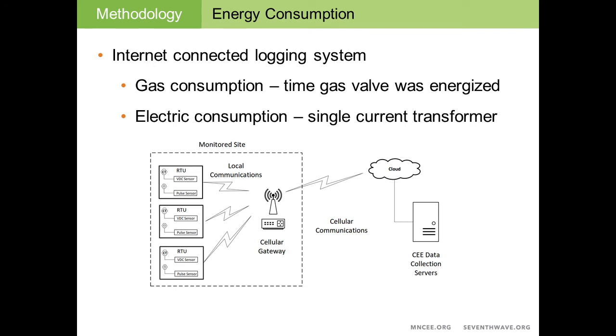The 2 main energy streams that we're looking for in rooftop units are the gas consumption and the electrical consumption. Traditionally, if you were to put a standard logger on the roof and install a gas meter, redo the gas lines in order to get the gas consumption, and then also install a power meter, that's going to be an extremely expensive endeavor when you start looking at the number of rooftop units and sites that we wanted to monitor. So CEE took a different approach where we decided to time the gas valve. By knowing how long the gas valve is operational, and by knowing the input rate of that gas valve, we were able to compute the energy consumption of the gas for the rooftop unit. And we also deployed a single CT transformer method to measure the energy consumption on the electrical side.